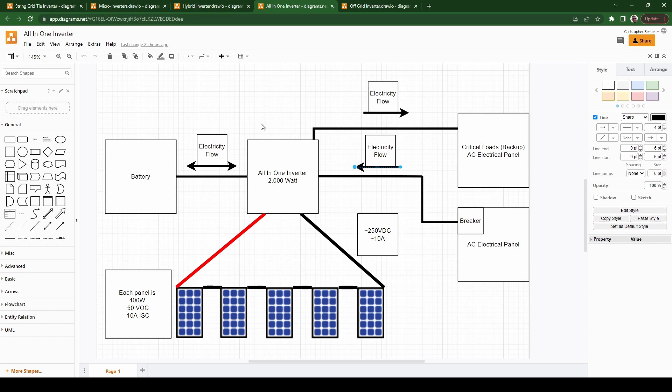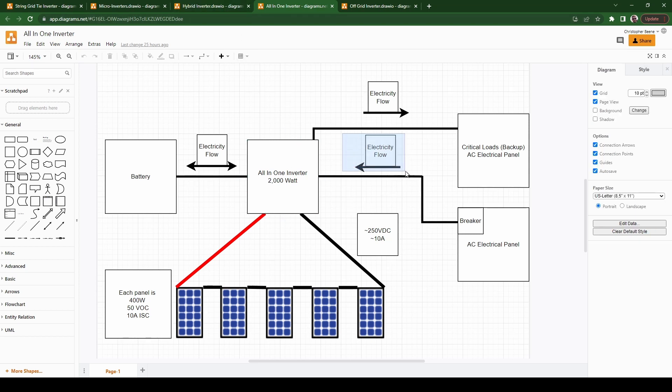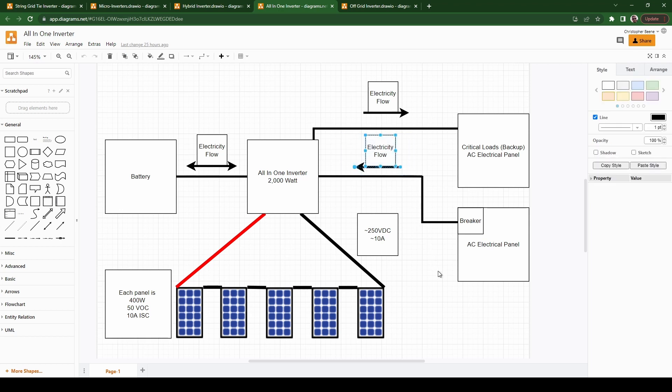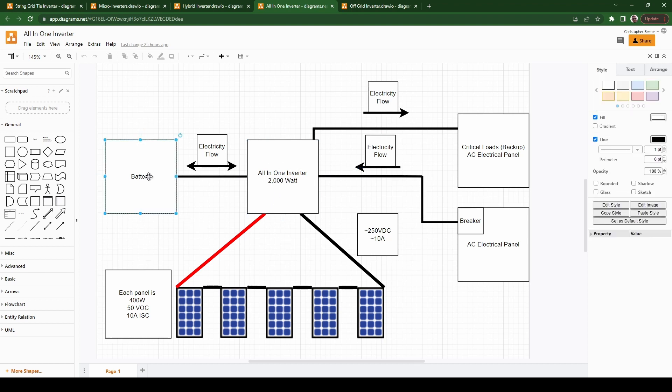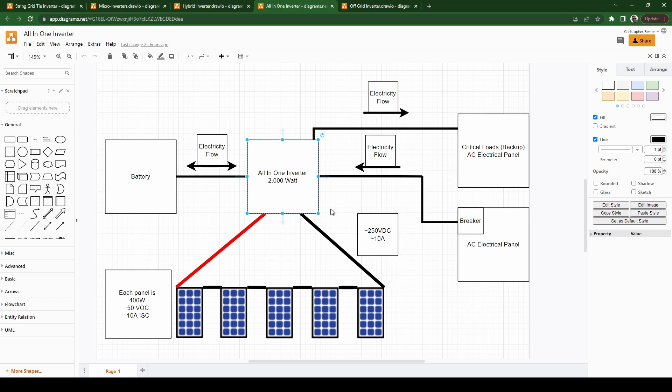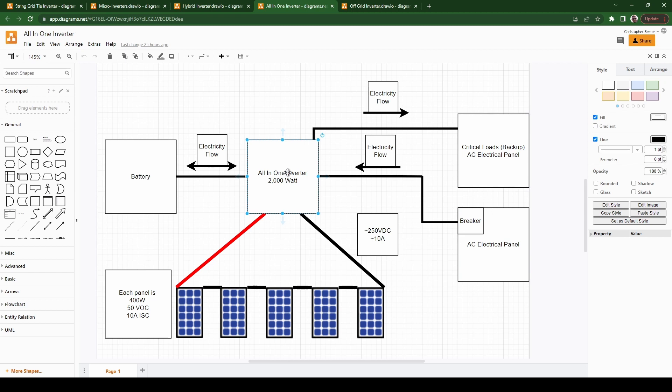All-in-one inverters is like what you would see with a Growatt or an MPP Solar. The big difference here between an all-in-one inverter and a hybrid inverter is that this here is only one direction. The electricity flows from the AC electrical panel, from the grid into the all-in-one. According to the electrical panel, this is an appliance. Typically they're configured where the battery and the panels are going to run your critical loads or your off-grid stuff as much as possible. If there's not enough power or the battery voltage is too low, the automatic transfer switch that's built into the all-in-one inverter will trip and you'll then be in bypass mode.